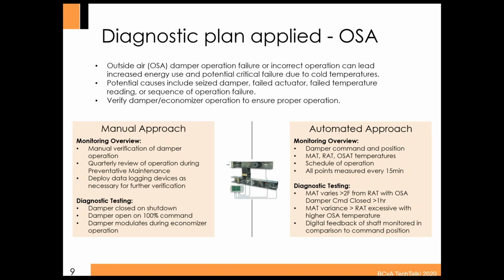A mixed air temperature variance that's much higher than your return air is also a potential issue with the damper. And so there's probably no less than half a dozen different types of analytics you can apply to this that use the data available on an ongoing basis in order to get a good understanding of whether your damper is operating in an ideal state. That's just an example of the pneumatic, more manual approach versus the automated approach, but still looking for the same outcome, which is: is my outside air damper working correctly?